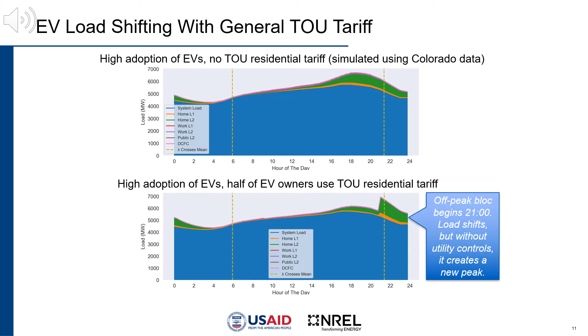The solution would be to find some way to spread charging start times over 2 or 3 hours after the off-peak period begins. One way to do this is with demand response. This is an emerging area of tariff design. It requires a smart charger, a device that can receive real-time instructions from the utility to change the level of charging. To illustrate, consider an L2 charger. A not-so-smart L2 charger will run at 6 kilowatts as soon as the vehicle is plugged in, and it will continue running at 6 kilowatts until the vehicle is charged. On the other hand, you can tell a smart charger to start running at a power level that is lower than 6 kilowatts. This allows the charger to increase or decrease its power instantaneously if a signal from the utility tells it to do so.